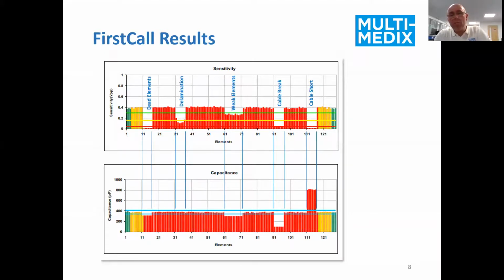Moving further over, if we lose a lot of the capacitance and all of the sensitivity, we can clearly identify, by understanding how reactance works with capacitance, that that's a cable break, so that's an open circuit. And if we get a spike in capacitance and no performance, that's another cable issue, where we've lost our sensitivity due to a cable short, so we're not able to transmit the electronic energy. I wish somebody had told me that right at the start, but I've made it really simple for our team, and we're here today to try and share that with you.